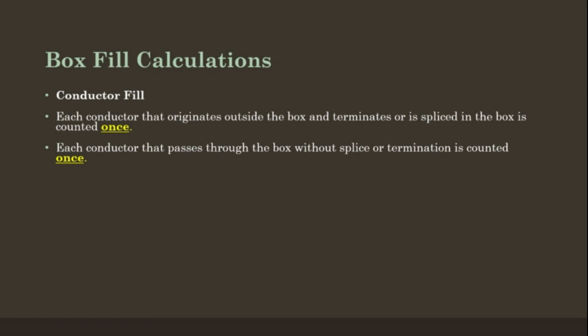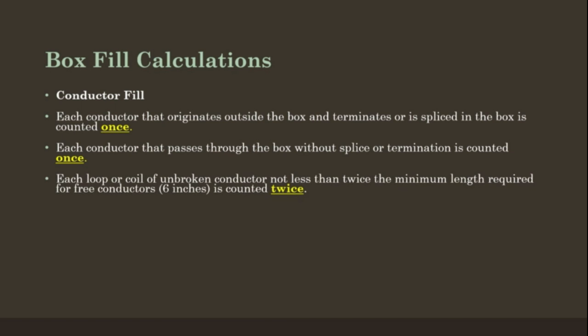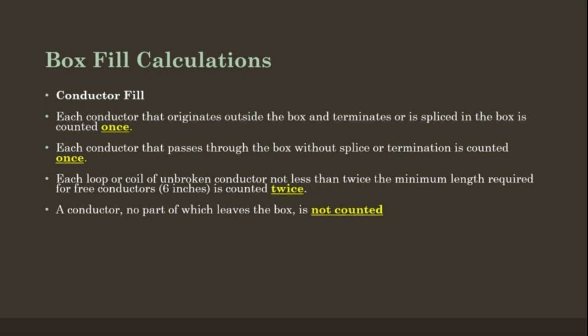Each conductor that passes through the box without a splice or termination is counted once. Each loop or coil of unbroken conductor, not less than twice the minimum length required for free conductors (6 inches), is counted twice. A conductor, no part of which leaves the box, is not counted.